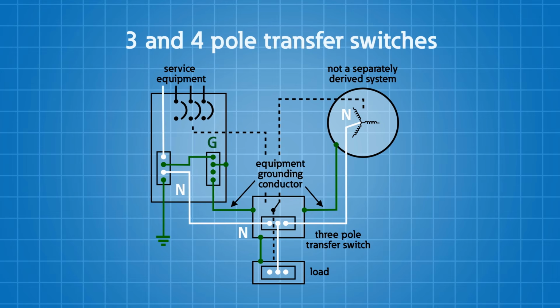Now, sometimes people will drive a ground rod and bond the generator frame or the structure to that ground rod, and that ground rod is supplemental. So it's not required by the National Electrical Code. It is a supplemental type of grounding. A purposeful connection between the neutral, that grounded conductor, and that ground rod system, the grounding system over there on that generator, may occur in the field, either on purpose or by mistake. The important thing to understand is when you make that connection, you've established a separately derived system.